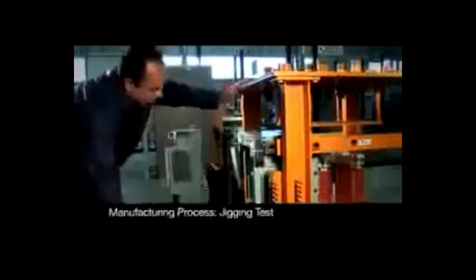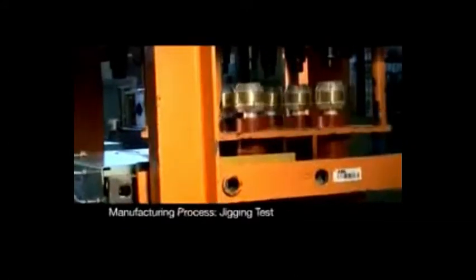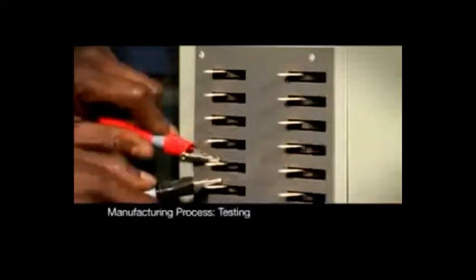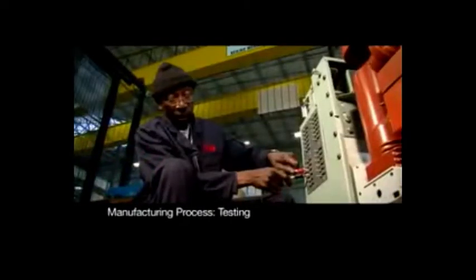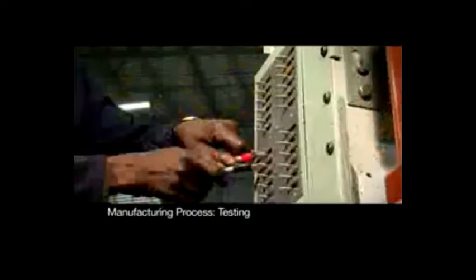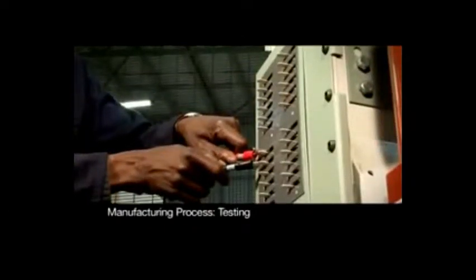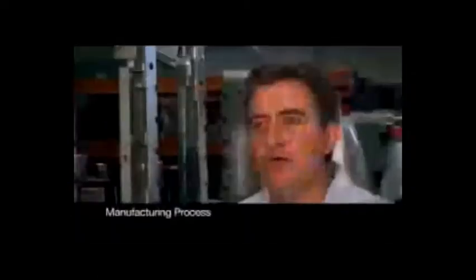The breaker will be lined up and the side swipes and interlocking will be checked to make sure that they comply. This stage of the process is where the high pressure testing, wiring and functionality of the unit are tested. A 2 kV test is conducted on the wiring and a 28 kV test is conducted on the riser and copper work to ensure the unit leaves the factory in a fully working condition. They go through all the normal SABS requirements at the end of the day to ensure that the equipment we're retrofitting is safe to the client and that it will work reliably.